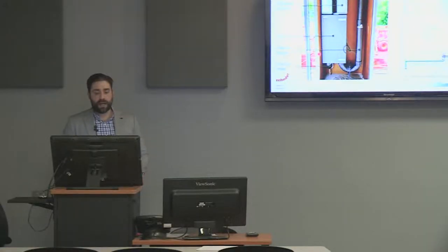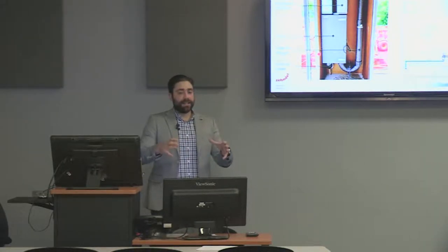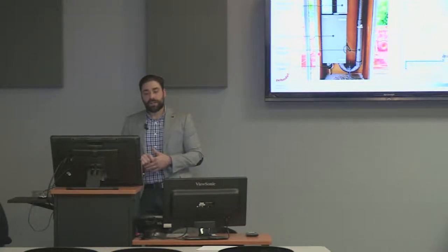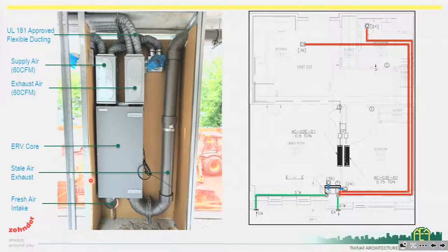So how are we doing it? We actually have a hybrid system — we're blending two approaches together. In each one of the residential units, we're islanding that unit, treating it as its own environment. We're installing a decentralized ventilation system inside each apartment, using the Zehnder ComfoAir 200 product, and that's going to be mounted on the exterior wall. So we have our exterior wall here, and that's where our Zehnder unit is mounted.